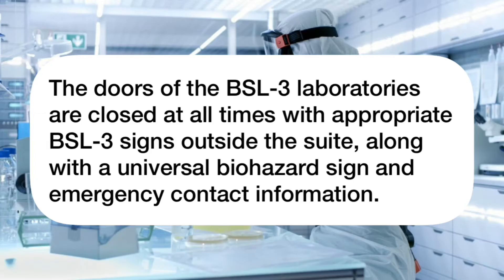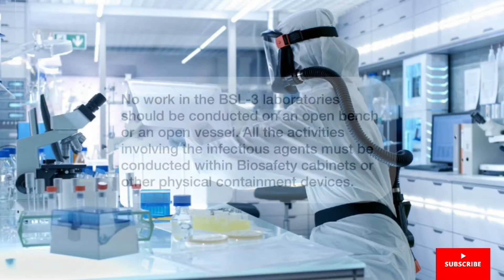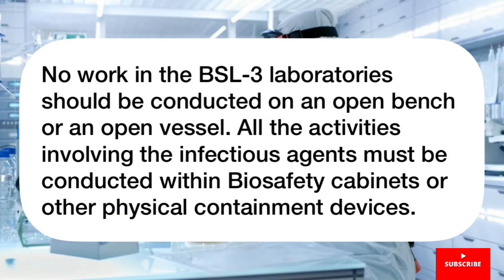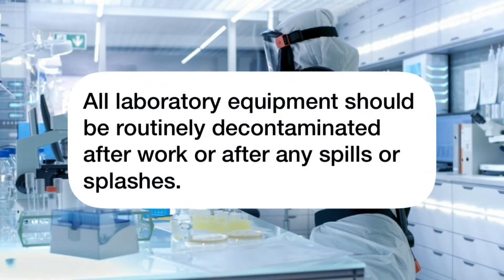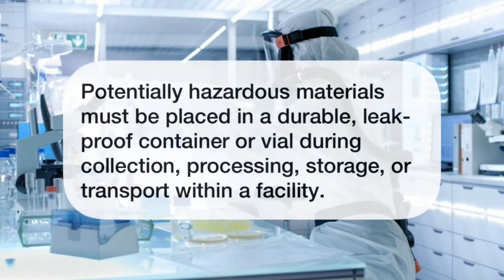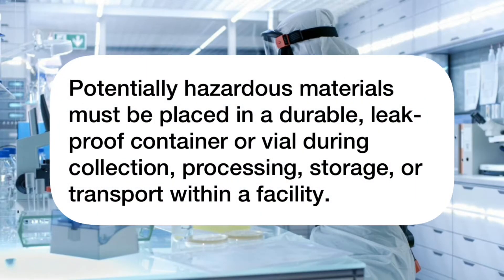Safety Practices of the Biosafety Level 3 Laboratories: The doors are closed at all times with appropriate Biosafety Level 3 signs outside the suite along with a universal biohazard sign and emergency contact information. No work should be conducted on an open bench or an open vessel. All activities involving the infectious agent must be conducted within a Biosafety Cabinet or other physical containment devices. All laboratory equipment should be routinely decontaminated after work or after any spills or splashes. Potentially hazardous materials must be placed in a durable leak-proof container or vial during collection, processing, storage, or transport within a facility.